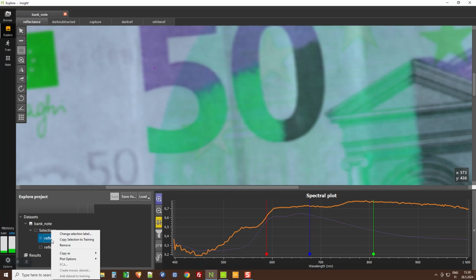So as a next step, I would actually change the lens. So now we have made a data acquisition with a 38-degree lens. We had a field of view which was about 10 centimeters for 1024 spatial pixels, meaning that I had a pixel size of about 100 micron. So I'm going to change the lens to use a brand new VNIR macro lens.